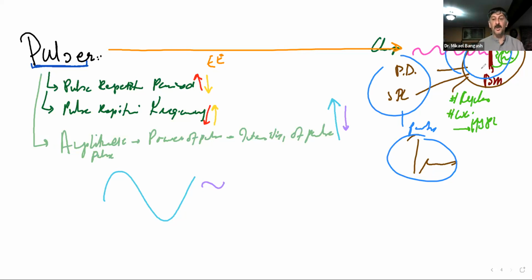How big the pulse is going to be in terms of time, or how big the pulse is going to be in terms of length, with respect to the pulse duration and spatial pulse length, is determined by things within the transducer. But how frequently the transducer will produce a pulse, or the time span between pulse 1 and pulse 2 and pulse 3 and pulse 4, which is your pulse repetition period, is determined by the pulser.